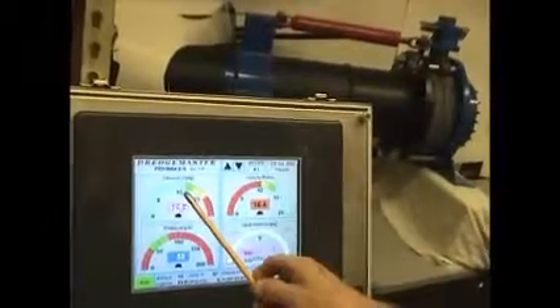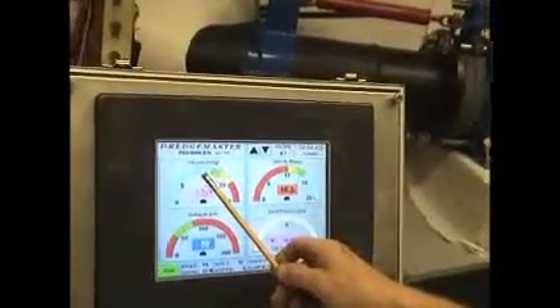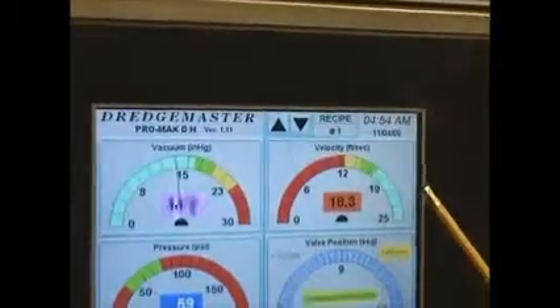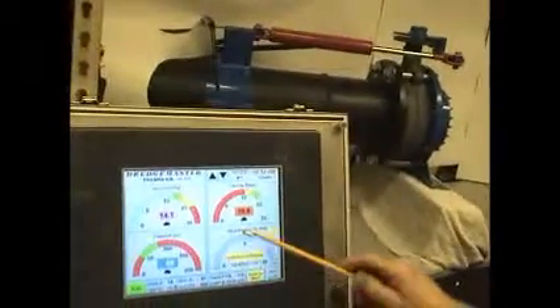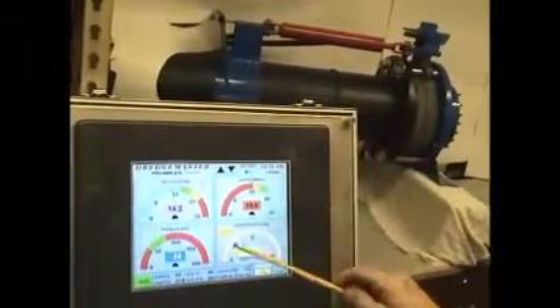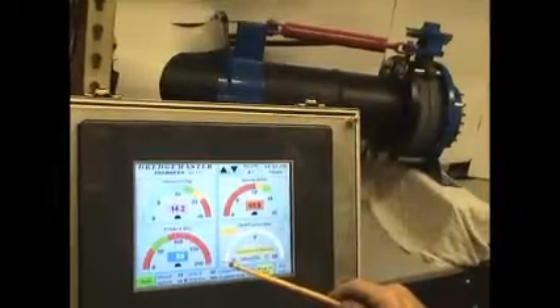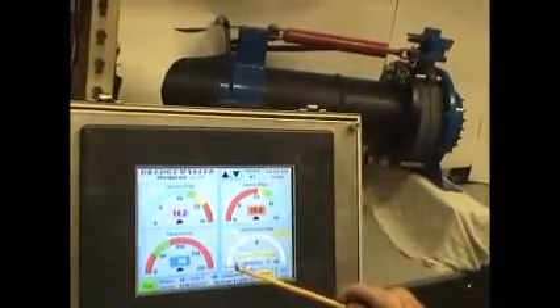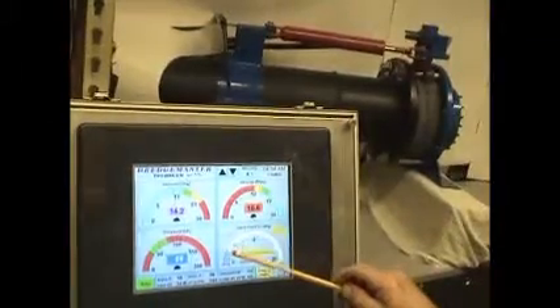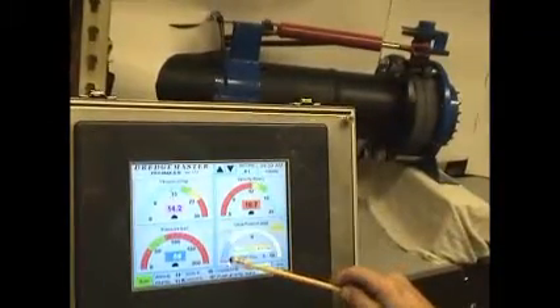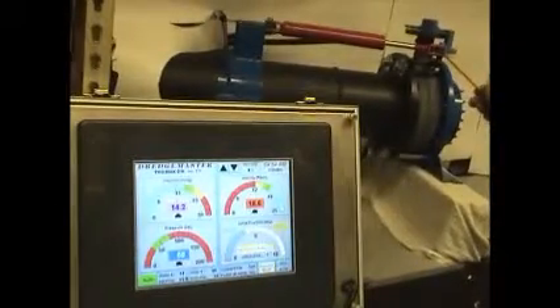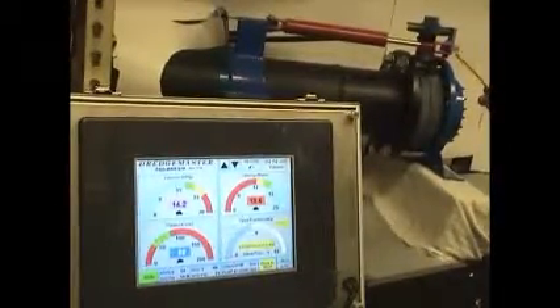So we can see our vacuum is dropping down into the turquoise range, and also our velocity. Our valve immediately opened all the way up. You can see on the gauge. Now the valve immediately closed all the way, and now it's starting to step itself open. It is starting to count how many of these steps it takes to go from fully closed to fully open. As you can see, the cylinder is constantly stepping itself open.